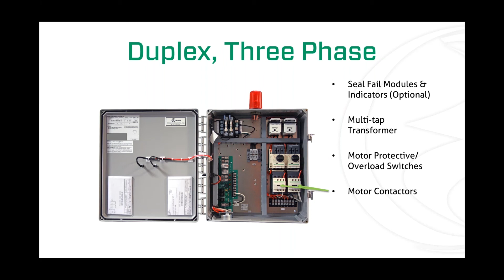The seal fail modules that I spoke of, here they are. We're going to look at the multi-tap transformer, there it is in the top corner. These motor protective switches that I mentioned, those are those little roll knobs that I was talking about. They just turn either straight up or they are 90 degrees over. Right now these are in the off position, it looks like. If they were straight up, they would be turned on. If they tripped for some reason, they would be at like a 45-degree angle there. And then lastly, right below that is the motor contactors.